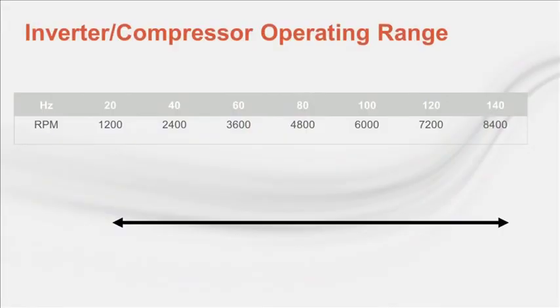This is a good spot to elaborate on the VRF variable speed compressor. Most VRF systems today feature one or more inverter-driven compressors. Most compressors have a design range similar to what I'm showing here. In this example, the inverter drive operates between 20 and 140 Hertz, which translates to 1200 to 8400 RPM. In the cooling mode, there's an optimum or most efficient speed for an inverter compressor. In this case, the optimum speed for cooling is between 2000 and 4500 RPM. In heating, this optimum range may be a bit higher.